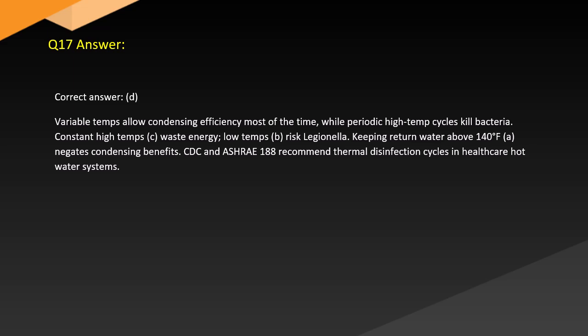Answer. Correct answer: D. Variable temps allow condensing efficiency most of the time, while periodic high-temp cycles kill bacteria. Constant high temps, C, waste energy. Low temps, B, risk Legionella. Keeping return water above 140 negates condensing benefit. CDC and ASHRAE 188 recommend thermal disinfection cycles in healthcare hot water systems.